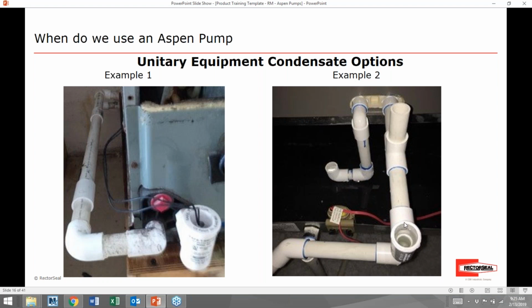On the right-hand side, we have a hybrid approach. It has a lot of safety features. So this particular drain line here is your primary drain line. Again, this would be typically plumbed somewhere inside the structure to some type of plumbing drain. Then we have a secondary drain line here. If this primary drain line were to get plugged, water would then flow out here into this pan. And then there is a drain line, a primary drain line for the secondary pan here. If for some reason that got plugged up, the water would rise up to the edge of the pan where our AquaGuard switch would then notify the system and shut it down.